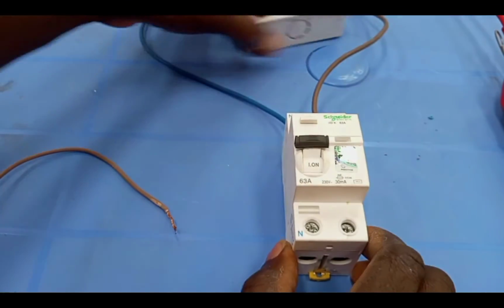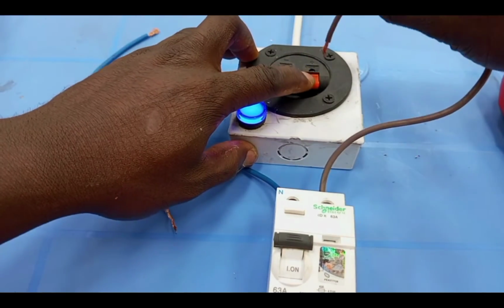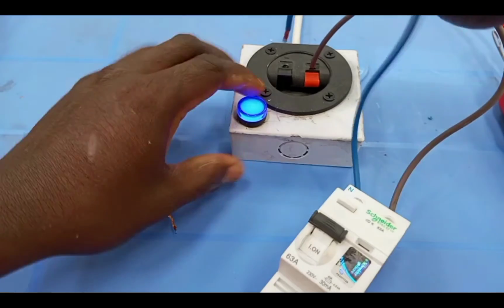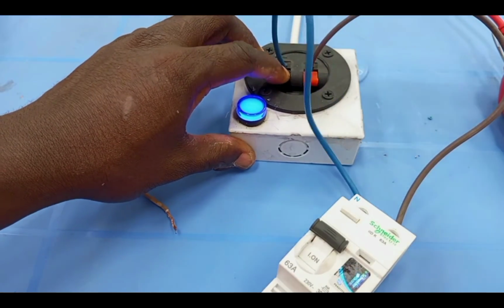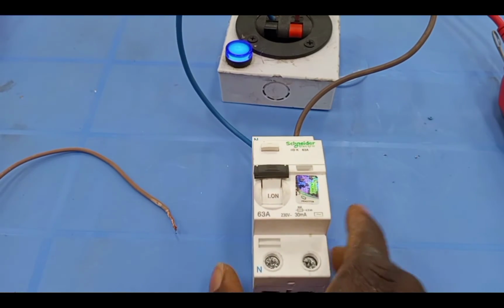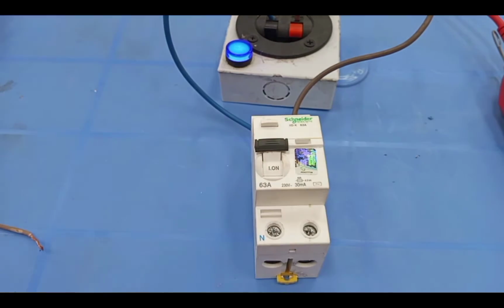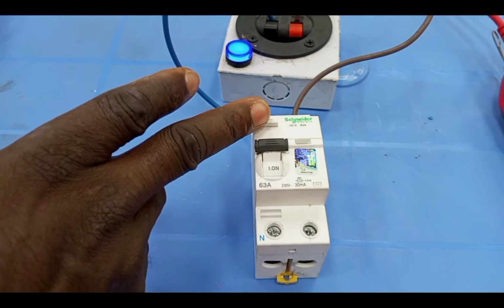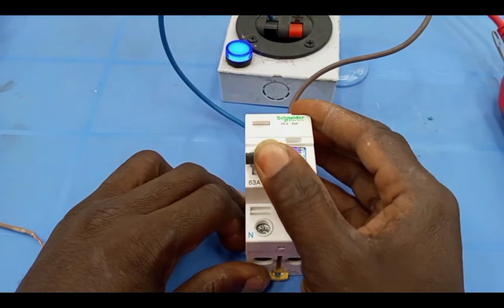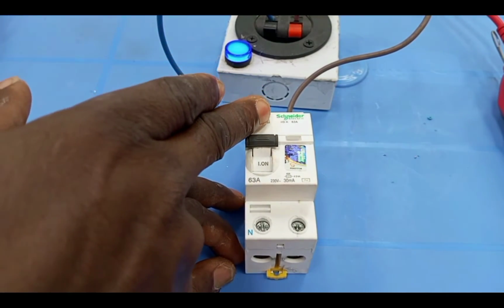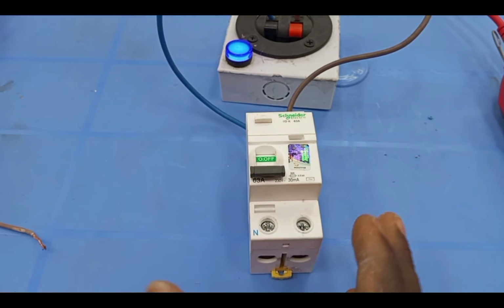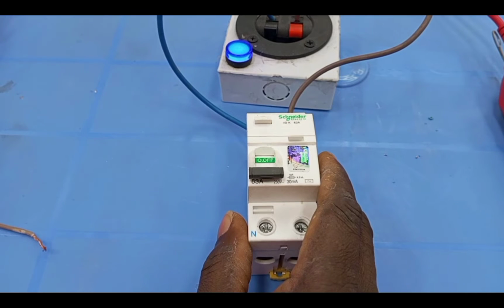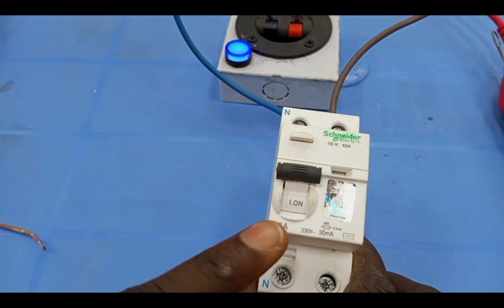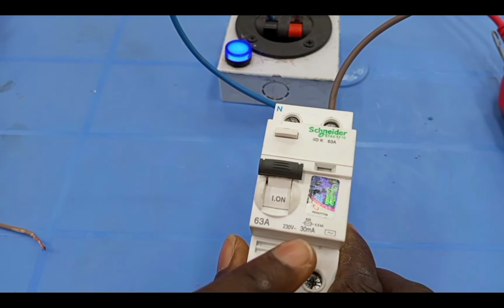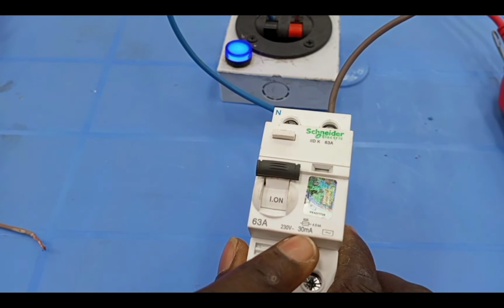Okay, so now I'm connecting this to supply. This is live, and then this is neutral. Okay, so it's on now. If you want to check whether the RCD is reliable or not, you just press the test button. All right, so on, you press this one, it should go off. All right, so now we are sure that this RCD is working. Now, the rating of this RCD is 63 amps. And then I also have 30 milliamp here.